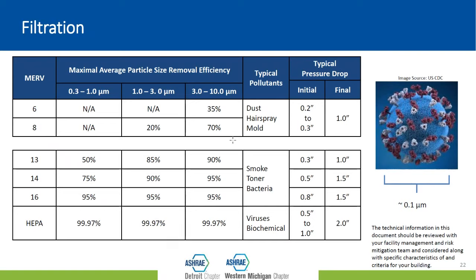I'd also like to talk just a little bit about filtration. There's been a lot of concern and interest about filters and filter MERV level and increasing MERV levels to improve our filtration. This table shows the efficiency of various MERV level filters. When we talk about a MERV level, the minimum efficiency reporting value for a particular filter, it's based on the efficiency of that filter removing particles in three distinct size ranges: between 0.3 and 1 micrometers, 1 to 3 micrometers, and then 3 to 10 micrometers, right?